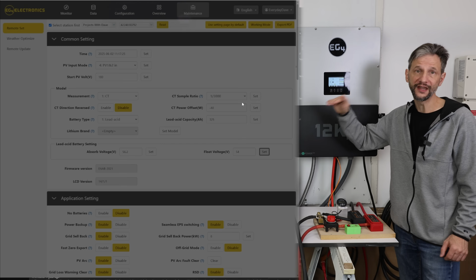I set the float voltage to 54 volts so that once the battery is fully charged, it won't hold it at a higher charge voltage or constantly run a charge cycle. Dropping down to the charge settings, we'll be using voltage instead of state of charge since we don't have communication with this battery. I set the charge current limit to 50 amps, which is 0.5 C for this battery, and that is the recommended charging rate. Of course, this inverter can deliver way more than that, so we need to make sure and limit it.